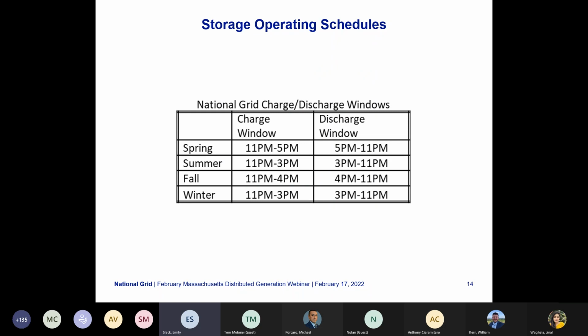The concepts of the schedule are that there is 24-hour-a-day operation of the battery permitted on a seasonally varying schedule. That schedule has mutually exclusive charge and discharge periods each day, such that at any given hour a battery could be either idle or charging if it's in a charge window, or idle or discharging if it's in a discharge window. The schedule outlines the permissible behavior in any given hour rather than any sort of dispatched or mandated operation. So within the confines of the schedule, there is flexibility to operate the battery as desired, so long as it doesn't attempt to discharge during a charge window or charge during a discharge window.